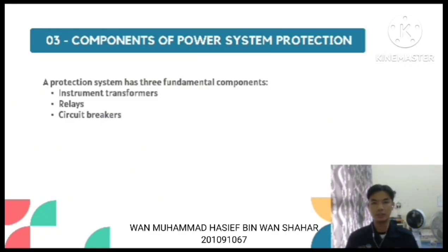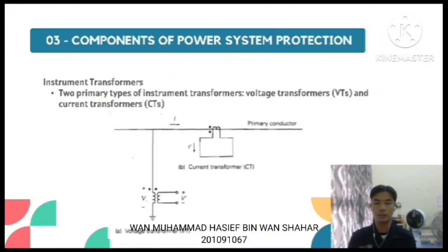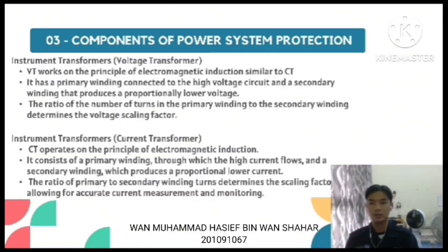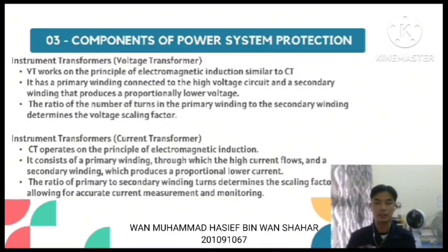For instrument transformers, there are two primary types: voltage transformers and current transformers. The VT works on the principle of electromagnetic induction, similar to the CT. It has a primary winding connected to the high voltage circuit and a secondary winding that produces a proportionally lower voltage. The ratio of the number of turns in the primary winding to the secondary winding determines the voltage scaling factor.